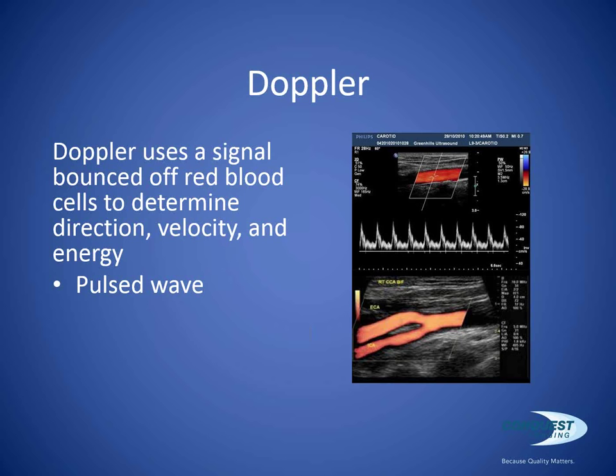What we do is we take a signal and send it into a blood vessel, and we bounce that signal off red blood cells. We receive that signal back, and we can tell by a frequency shift what direction that blood is going in and how fast it's going. There's various forms of Doppler. The top Doppler that you see is a combination of color Doppler and pulse wave Doppler. The bottom image is something that's called either power or energy Doppler.